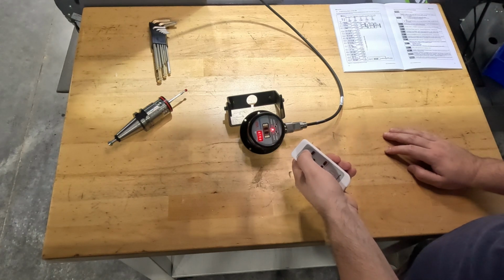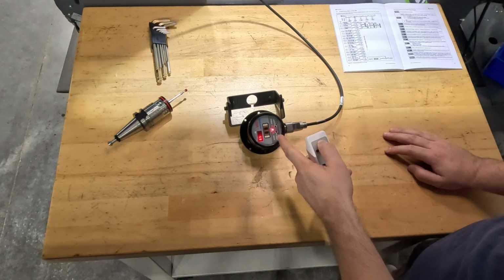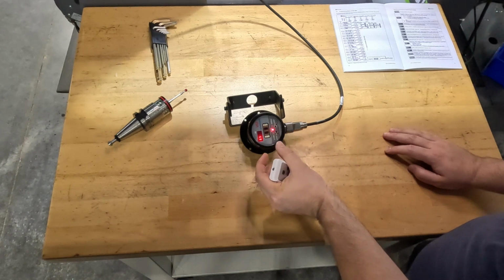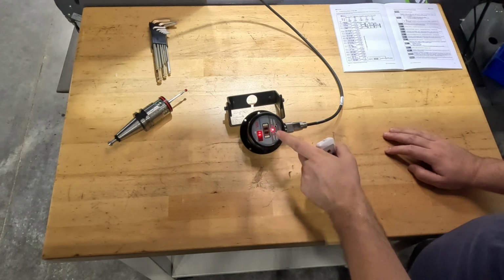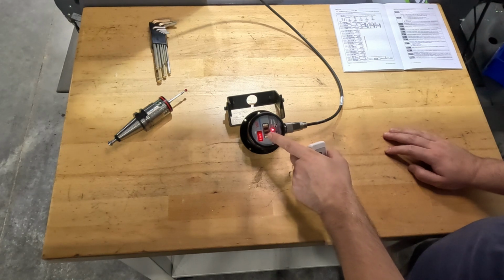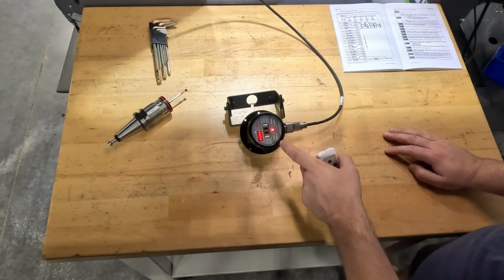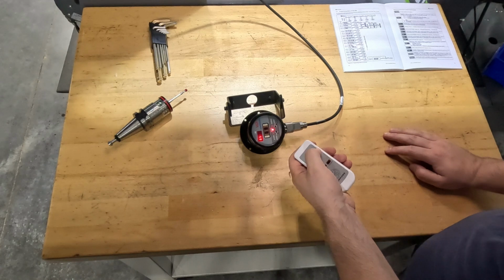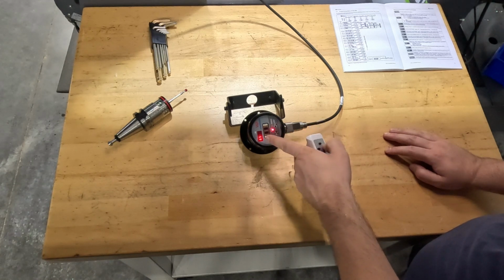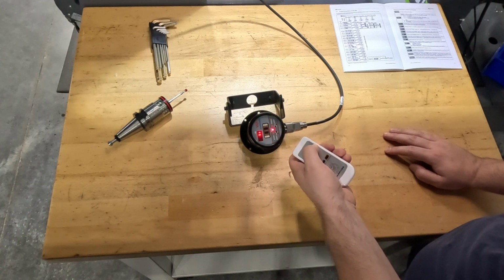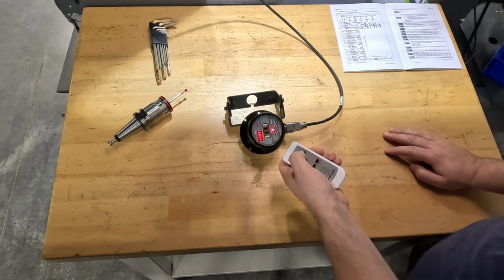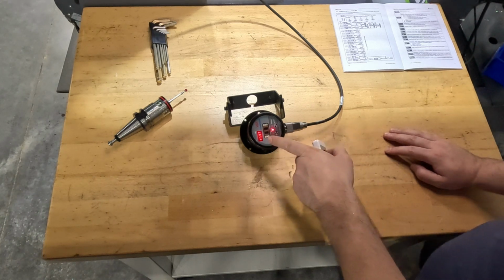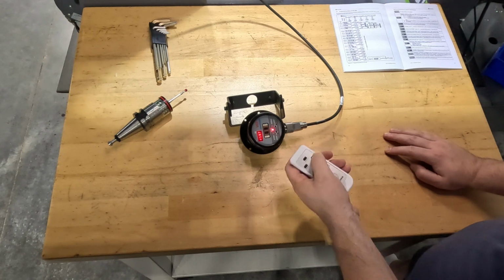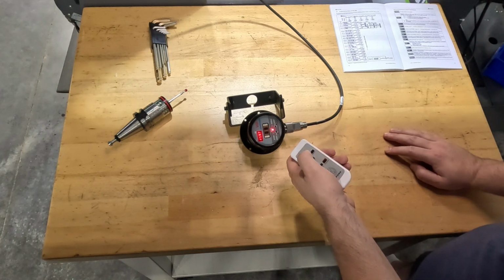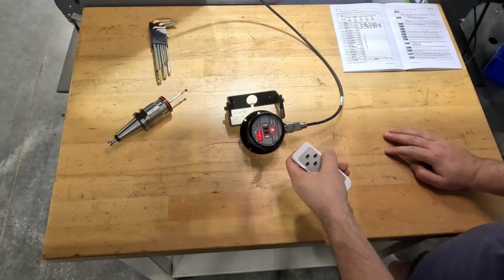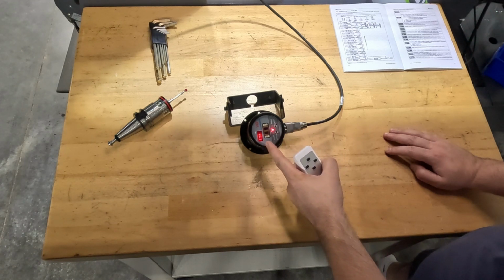I'll hit select plus one time, and that changes to BS. If you leave it sit here for a couple seconds, it'll start displaying a name. It says base station programming in this case. So if I hit enter plus to go into it while it's saying that name, it's just going to go back to BS, and then you hit enter plus a second time, like so. R107, in this case, is our firmware version, so that's not a setting we can change. Hit enter plus again. Type V is our first setting.